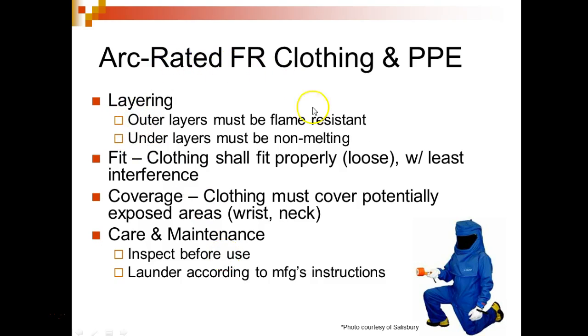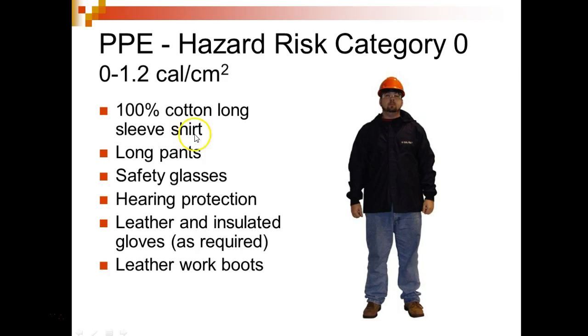Of course, arc rated, and we're not going to get into all this. So notice this is 0. This is basically what we're supposed to wear in this class right here. We're supposed to wear long sleeve shirts, long pants, safety glasses, hearing protection, leather gloves, and leather work boots. So that's what we should wear in motor control. Okay. But we don't. We're only at 24 volts here.